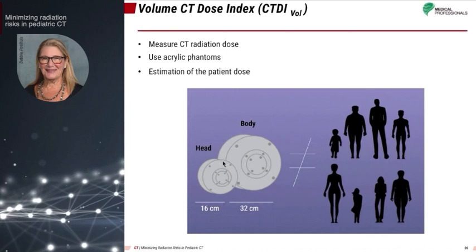Reported in milligray, volume CTDI is a standardized measure based on manufacturer measurements for different protocols. This is determined with acrylic phantoms that are either 16 centimeters or 32 centimeters. Again, it is not the dose to the patient, but provides a sort of estimation.